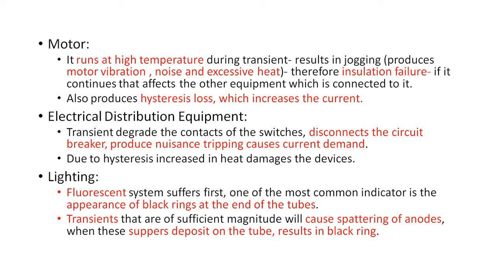Lighting: the fluorescent system suffers. First, one of the most common indicators is the appearance of black rings at the end of the tubes. Transients of sufficient magnitude will cause sputtering of the anodes, and when this material deposits on the tube, it results in a black ring.